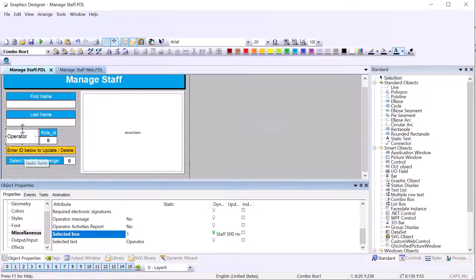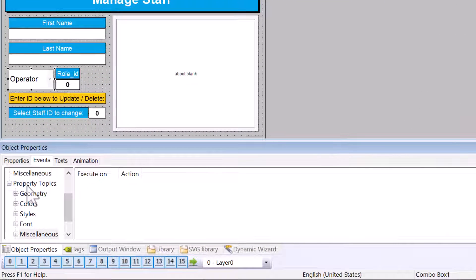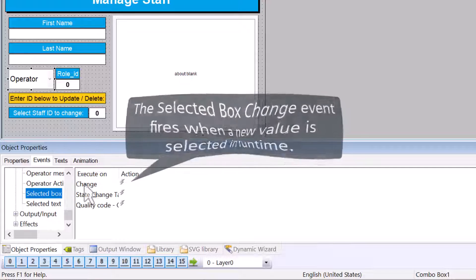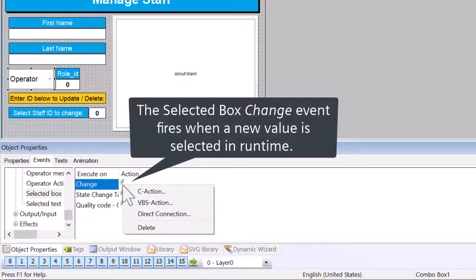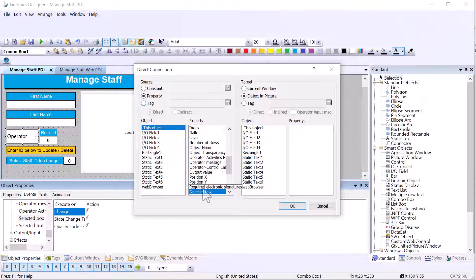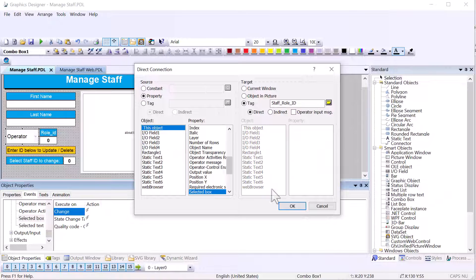The other thing we want is for a selection change to write to the tag. On the Events tab, under Property Topics > Miscellaneous, there is a 'Selected Box Change' event that fires when you make a different selection. I'll right-click and do a direct connection so that whatever you select goes directly into our staff role ID tag. Hit save.